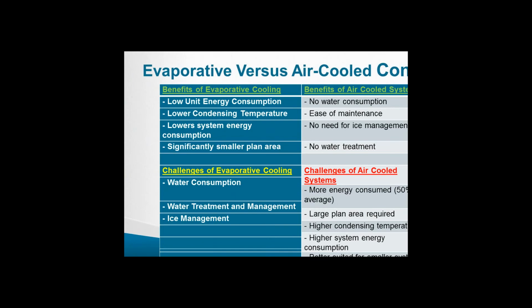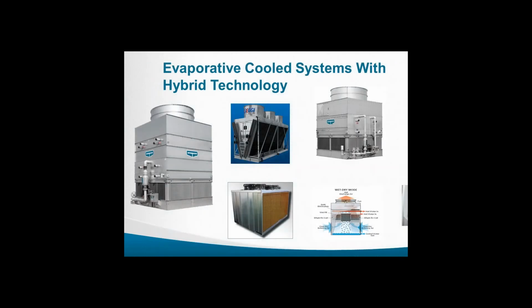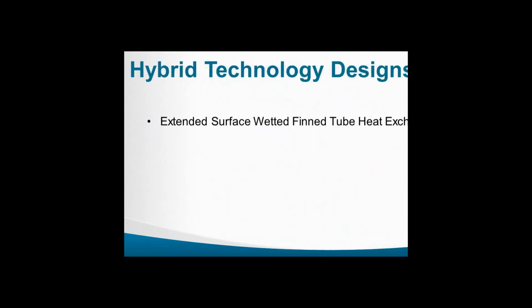Air-cooled is kind of the opposite. There's no water consumed. It's easier to maintain, no ice management issues, and there's no water treatment. But then you have, you know, 50% more energy, big plan areas, high condensing temperatures, and higher system energy. So it's a trade-off. So you see a lot of equipment being developed that has the combination. This is the hybrid technology. And this is what I'll go over.